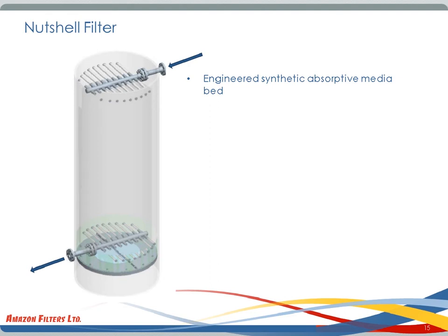While traditional nutshells are most common onshore, offshore we increasingly see synthetic or engineered nutshell medias which can offer much higher absorptive levels and allow higher throughputs. These are used offshore where space and weight are a constraint, since space and weight are not the best aspects of nutshell filters due to the low flux rates which we must flow the water through.